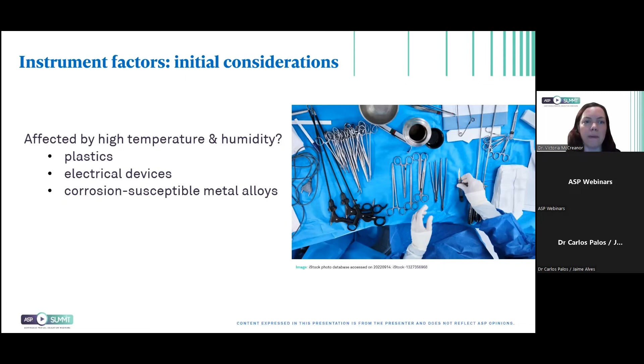Moving on to the instrument factors relevant to the evaluation - the first thing you'd probably need to consider is context specific: what types of instruments are you using? Because if they're made of plastics, or you've got electrical devices or corrosion susceptible metal alloys, those things are affected by high temperature and high humidity, and so they may be damaged in a steam sterilizer, for example.